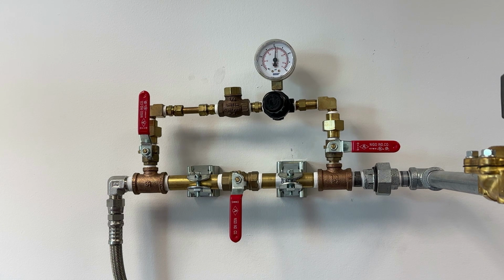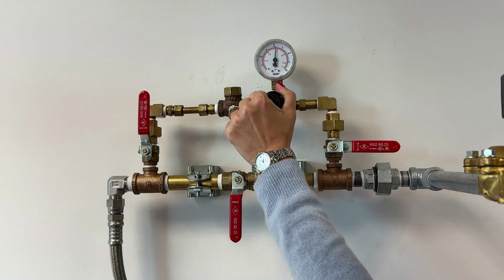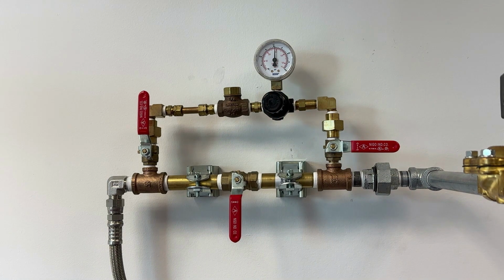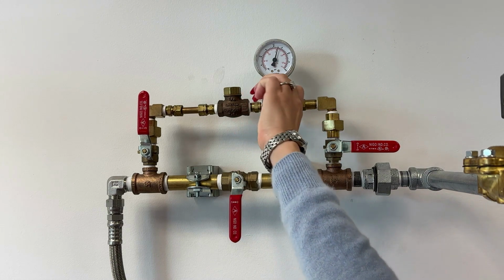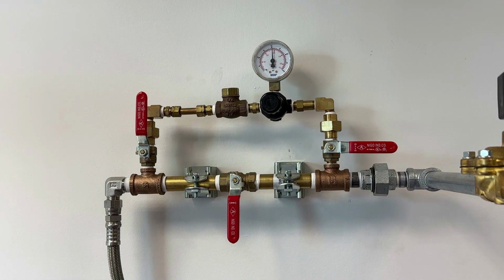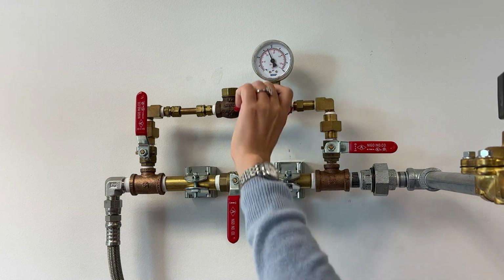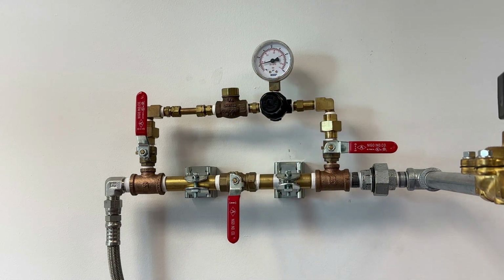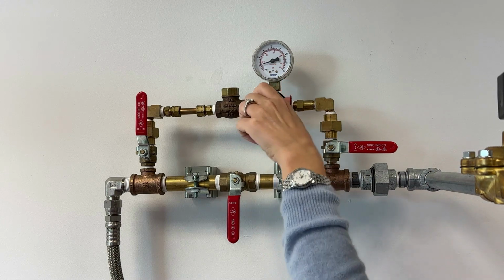If the sprinkler system operating pressure is to be different from the factory setting, you will need to field adjust the pressure settings. To field adjust the pressure settings of the Potter Advanced Air Maintenance Device, first ensure that the inlet ball valve is open and the outlet and bypass valves are in the closed position. Then, pull out on the adjustment knob of the regulator until it clicks into adjustment position. To increase sprinkler system pressure, turn the adjustment knob of the regulator clockwise until the desired pressure is achieved. To reduce sprinkler system pressure, turn the adjustment knob counterclockwise to at least 5 psi lower than the desired pressure. Then adjust clockwise to desired pressure.